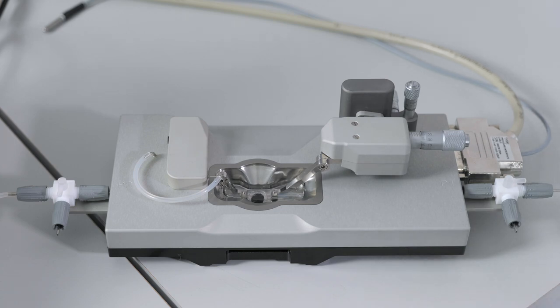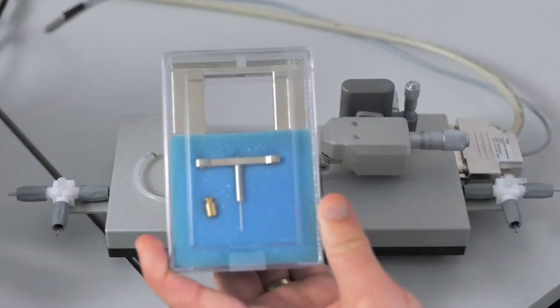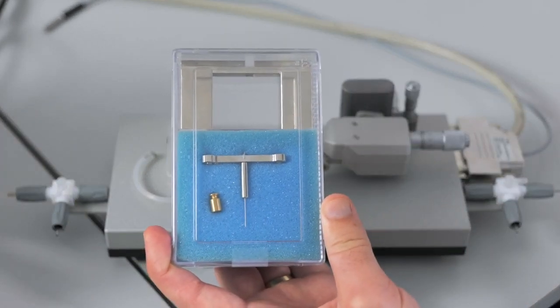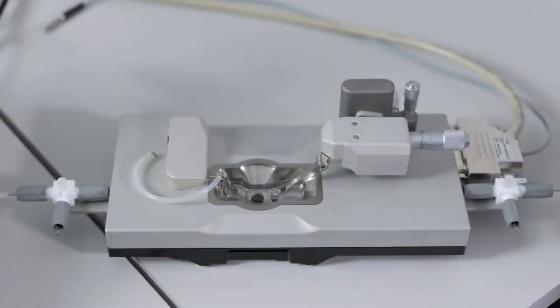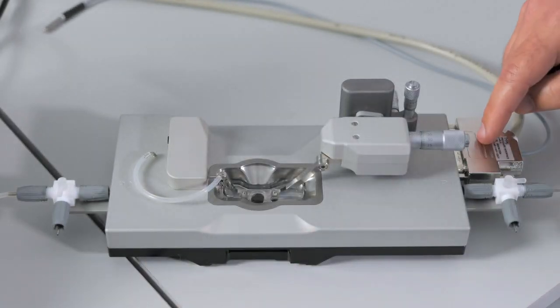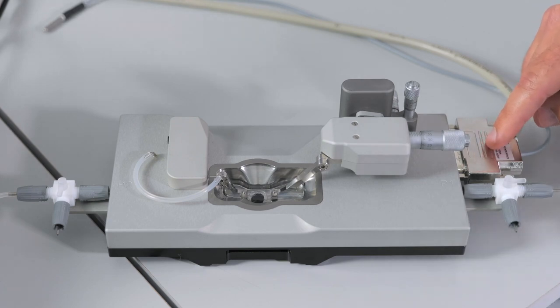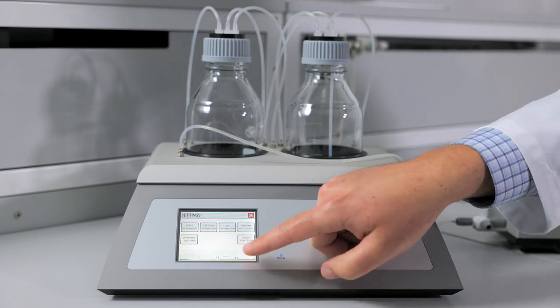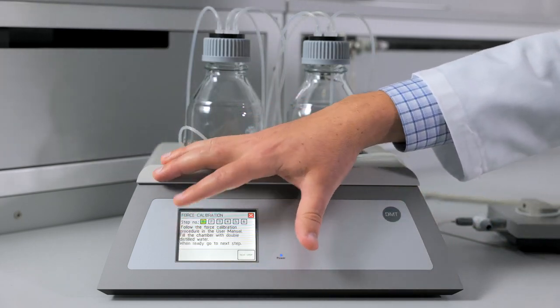This is important to perform in order to have accurate force readings, as you are using the force transducer to apply standardized stretch between each vessel of your experimental group. To do this procedure, you will need the calibration force kit that came with your 114 system, and make sure that you have your myograph cable connected to your interface. We will go into the settings menu and go into the force calibration.